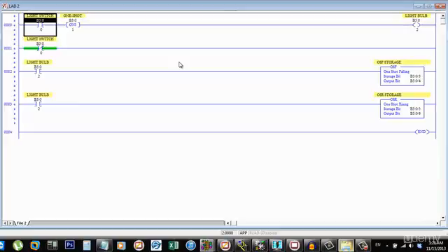So if you want the PLC to do something one time instantaneously, to check a reading, to record a value, and you only want it to happen exactly one time when you push a button, how would you program that? Because when you push that button, the PLC is going to scan 10, 15, 20 times, and it's going to do that action that you only wanted to happen once several times over. And the answer is this instruction right here.